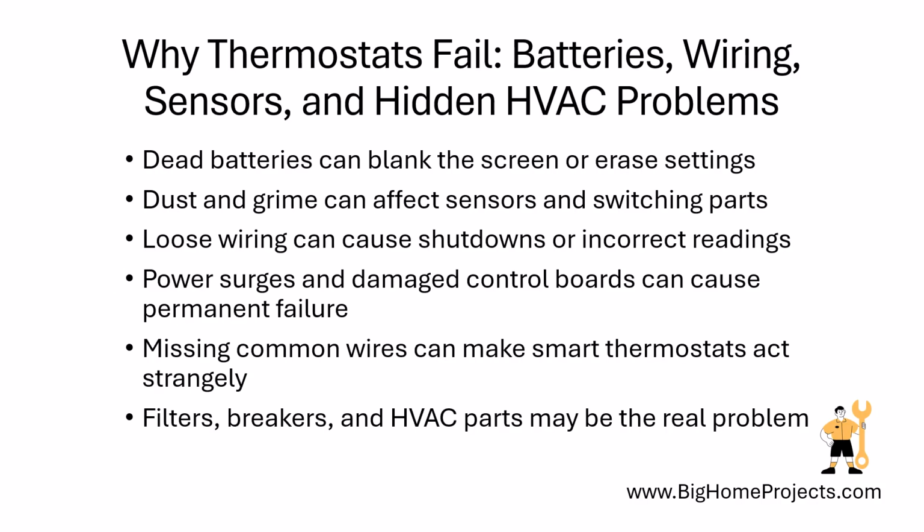The most common cause of failure is weak batteries, which can make the screen go blank or cause the thermostat to forget its settings. Dust and grime can also collect inside older thermostats and prevent their temperature sensor or switching parts from working correctly. Loose wires may cause random shutdowns, incorrect temperature readings, or no response when you change the setting. A power surge, short circuit, or damaged control board can permanently harm the thermostat.